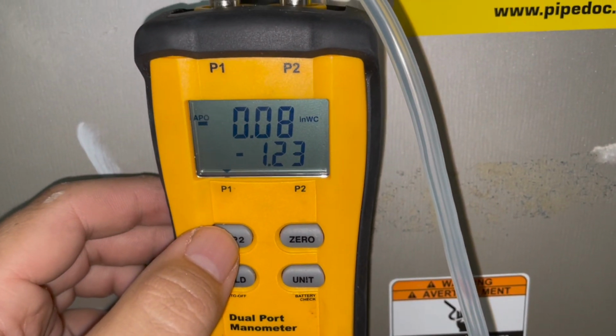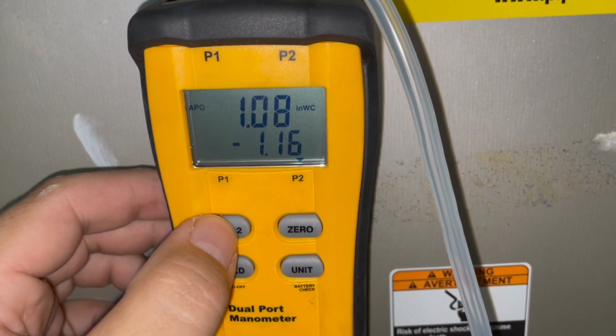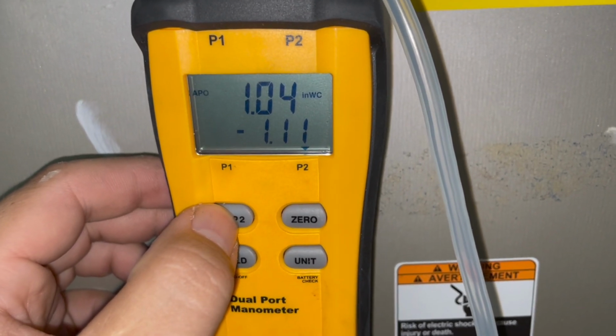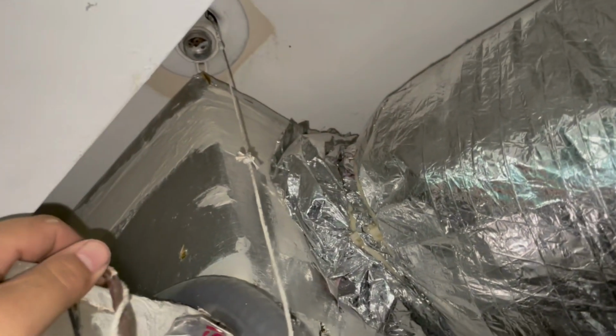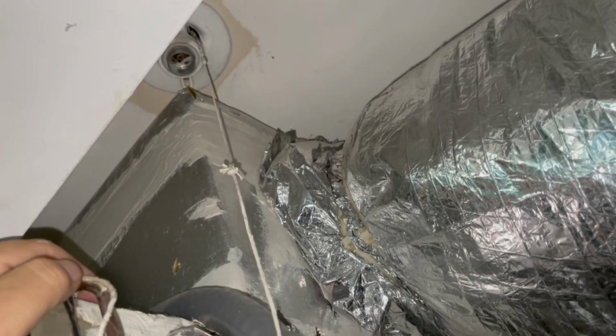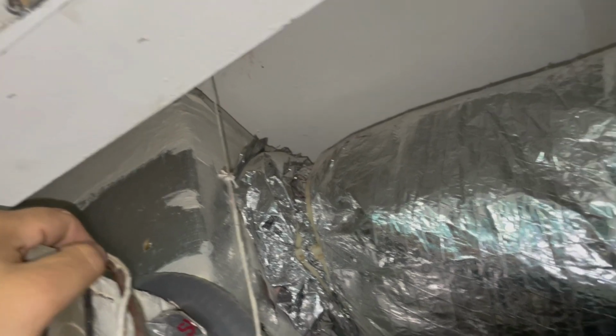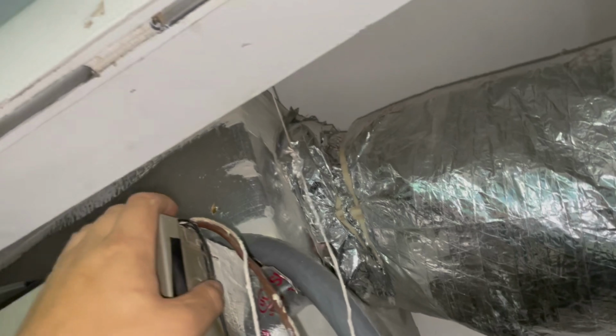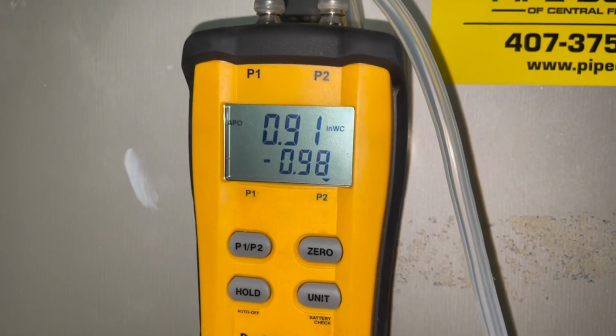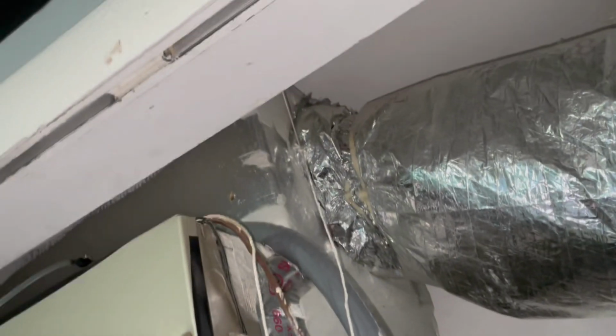So yeah, my total static is 1.23. Return side is 0.08. Supply side 1.08, 1.04. So he's got static pressure issues. He needs more supply. I think it needs to come out further than just a foot off of the air handler, ideally, before you have supplies coming off of it. Oh man, these don't look good. Guess that feeds this. So yeah, I think he just needs more supply air, according to this anyways. Almost 1 inch of water column just on my supply side.